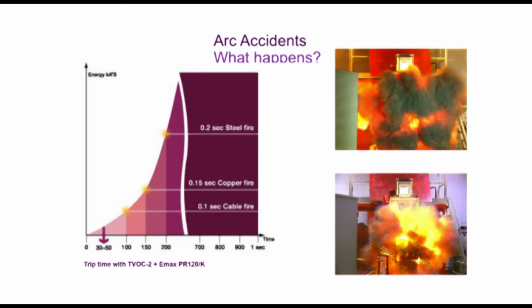It's interesting to note, based on this timeline against the energy that's being plotted, if you look at anything after 50 milliseconds or 100 milliseconds and above, you start seeing cable fire, copper fire, and sheet metal fire. So what we're saying is with the TVOC2 arc guard system, we can trip the breaker within 30 to 45 milliseconds.